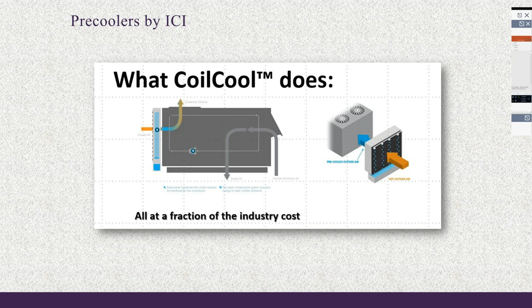Pre-coolers: we have already installed 3 by ICI for this project, with 3 additional to be installed soon. I'll speak more about these in our next webinar as we get to see their function. But pre-coolers in general increase cooling capacity by reducing the condensing temperature and the cooling load. They cool the air entering the condenser coil of the air conditioning unit, which increases the cooling capacity of the unit.